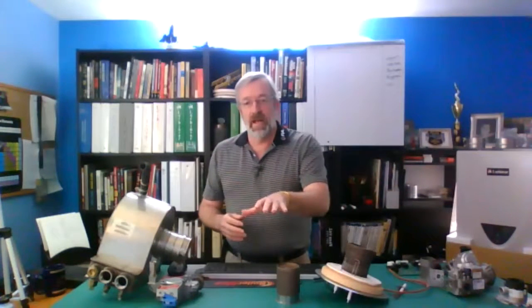A bad ignition cable, what that really can lead to is some intermittent flame failure ignitions type of scenario where sometimes it lights, sometimes it doesn't. It's just messing with that signal there and that connectivity. So that walks you through there. If I had gas and I've got spark, where's my next? Where am I looking for next?